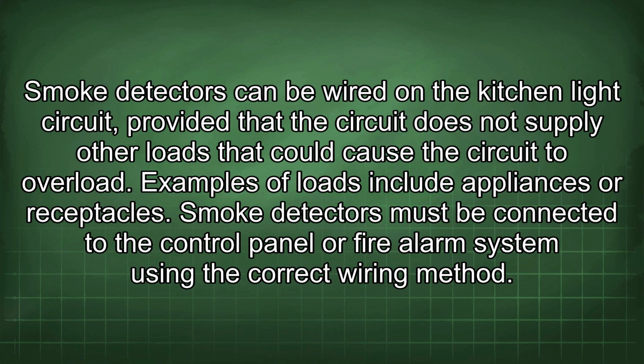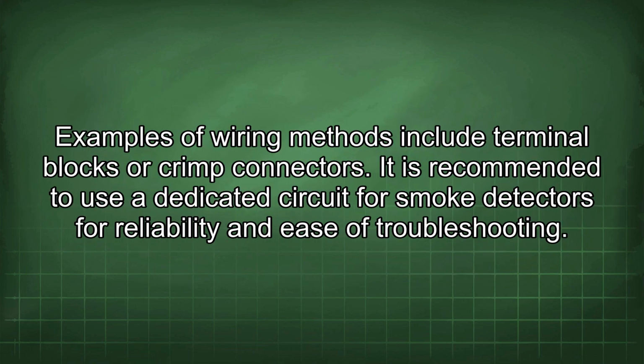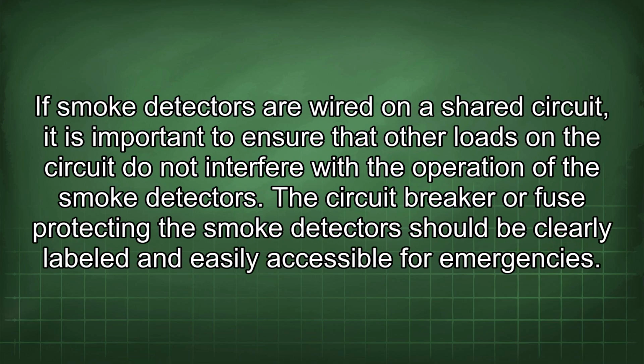Smoke detectors must be connected to the control panel or fire alarm system using the correct wiring method. Examples of wiring methods include terminal blocks or crimp connectors. It is recommended to use a dedicated circuit for smoke detectors for reliability and ease of troubleshooting. If smoke detectors are wired on a shared circuit, it is important to ensure that other loads in the circuit do not interfere with the operation of the smoke detectors. The circuit breaker or fuse protecting the smoke detectors should be clearly labeled and easily accessible for emergencies.